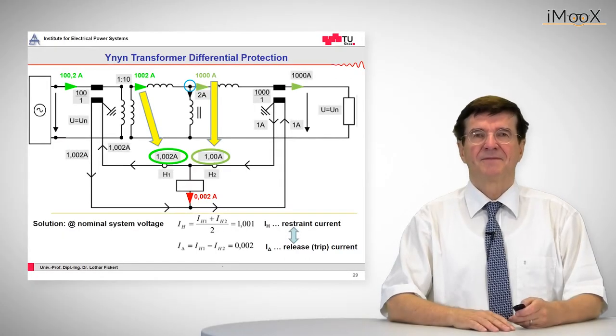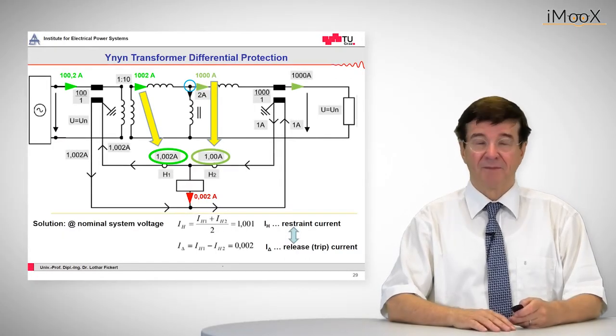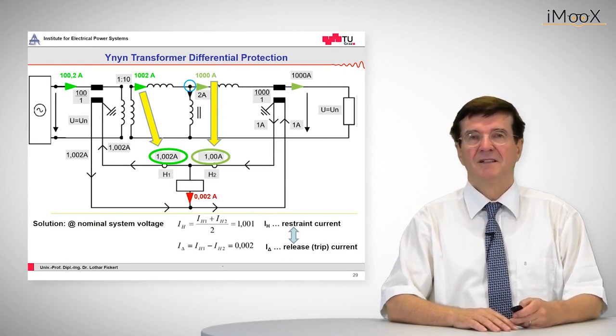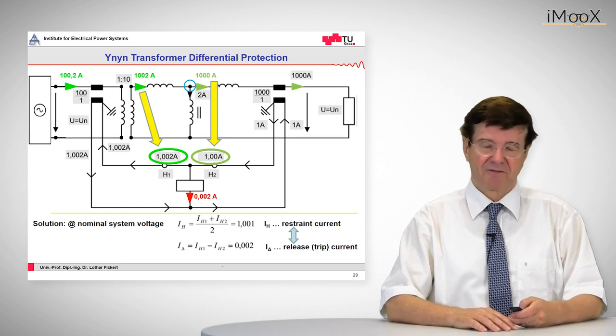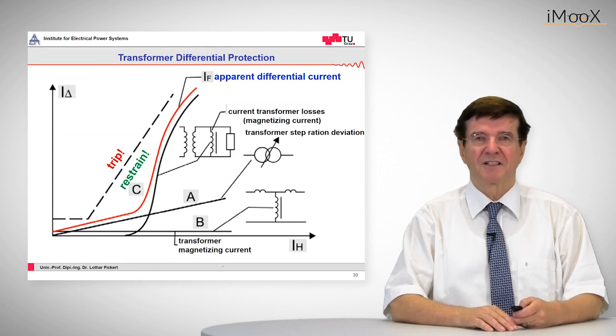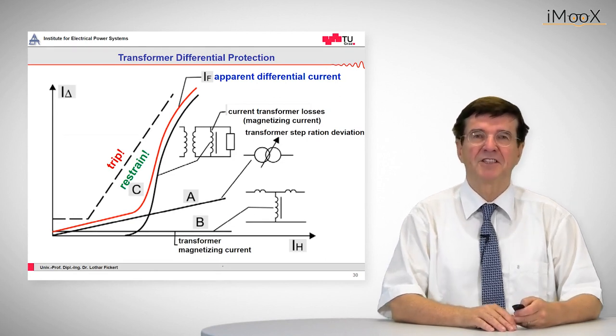So in this case it was shown that the magnetizing current of a current transformer leads to some apparent differential current. So there are other sources for apparent differential currents that may appear in the operation of the object.